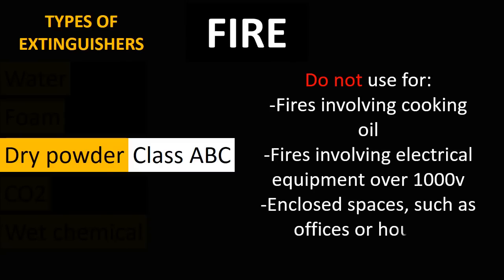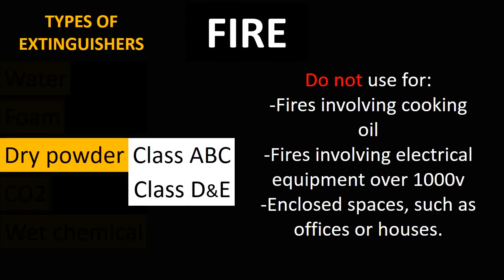Do not use dry powder type fire extinguishers for fires involving cooking oil, fires involving electrical equipment over 1000 volts, or in enclosed spaces such as offices or houses, as the powder can be easily inhaled and the residue is very difficult to clean up. Dry powder fire extinguishers can also be used on some electrical fires, and specialist dry powder fire extinguishers are used for flammable metals. Thus, dry powder fire extinguishers can be used on Class A, B, C, D, and E fires.